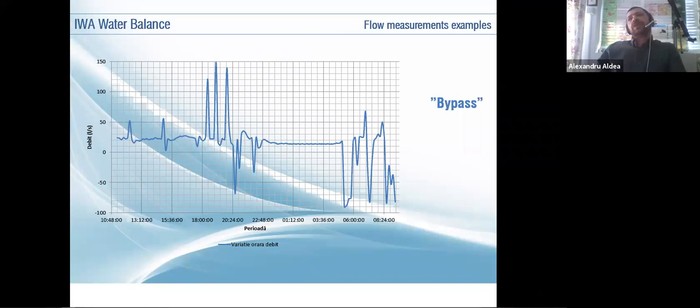So the official explanation given by the water utility at first was, okay, there is no problem, this is water hammer. I disagreed a little bit. I said, if this is water hammer, then you have some problem in your network. Let's make another measurement. And after 5 minutes, I found out what it was.